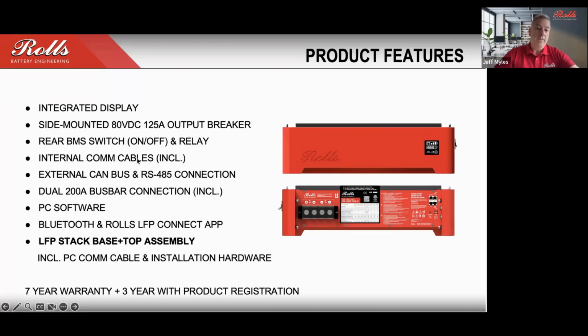The reason why we've done this is to allow, in the case of an installer, to be able to check those units and to ensure that the units are going to be balanced before you take them on site for an installation. And just as an example, if you were doing an installation that may be in a remote application, and you want to ensure that all of the components are ready to go to be able to do that install, you can verify that state of charge and voltage on each battery before you take them on site by simply taking them out of the box, powering on the BMS switch, and then you can see right away what the state of charge is for each unit.